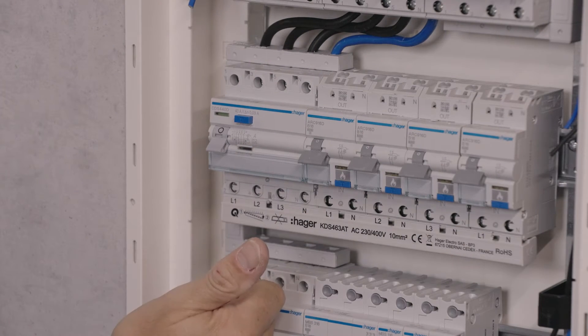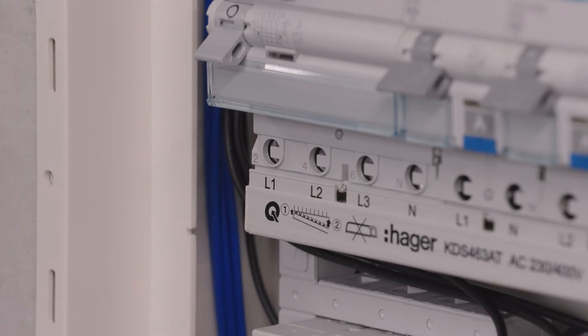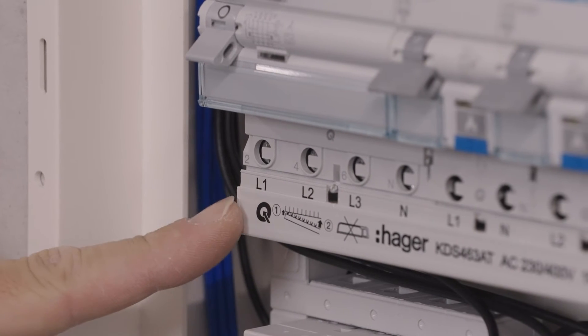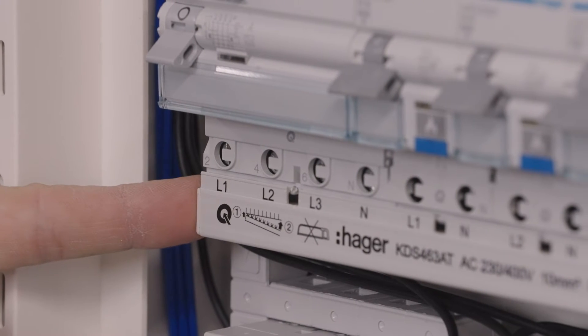Then plug in the horizontal bus bar without any tools and you're done. Once plugged in, there's no need to tighten the screws and no risk of forgetting to tighten or failing the contacts. For safety reasons, we highly recommend using only original bus bars marked with a Q icon, in order to avoid damage to the terminals and the risk of incorrect electrical connection.